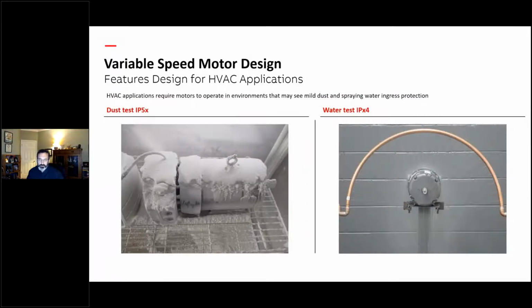This is what IP54 is, if you're not familiar with the testing. It's actually a lot more severe than you would typically see in an HVAC system, but it gets you your worst case. You know, if it's a condenser fan motor, or it's outside, or there's a lot of dust in the air, then that's why it is. So basically what you do is, this is a little vacuum hose. You have to attach a vacuum hose, you put it in the dust chamber, you pull a vacuum on the inside of the motor, and no dust can get on the inside.